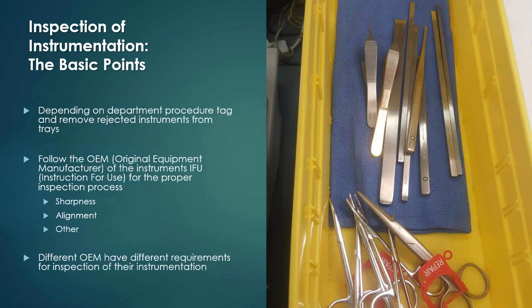So, depending on your department procedure, tag and remove rejected instruments from trays. I've been in facilities where the OR actually has the ability to do this, or SPD, or both - so make sure you're looking at your procedure to ensure you're doing it appropriately. You also want to follow the OEM, the original equipment manufacturer, of the instrument's IFU, instructions for use, for the proper inspection process. Different OEMs have different requirements for inspecting their instruments, so make sure you're looking at the list of what you're checking for - it could range from sharpness to alignment or other areas on the device.